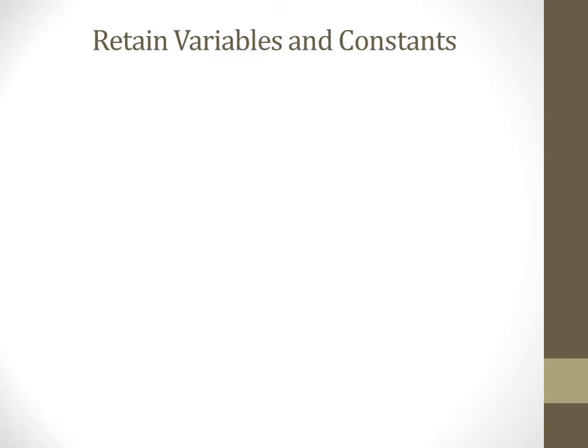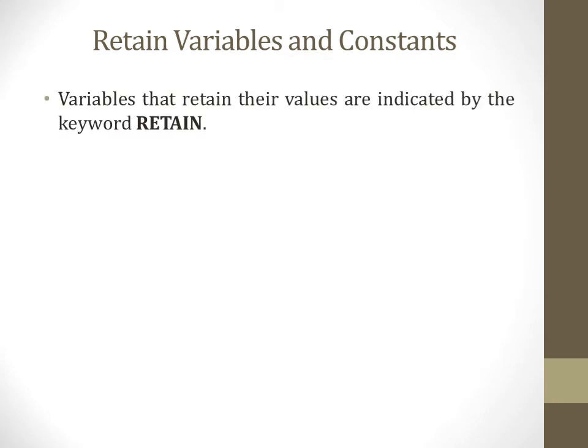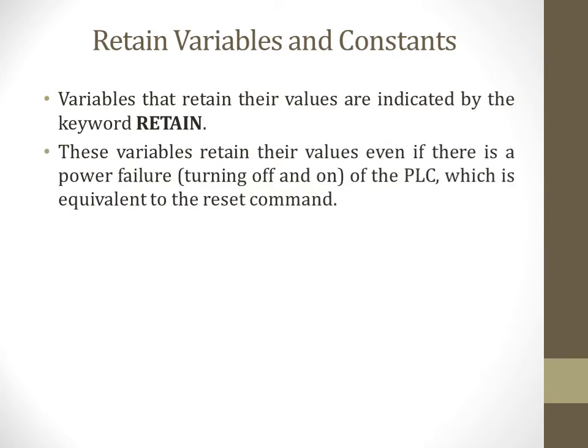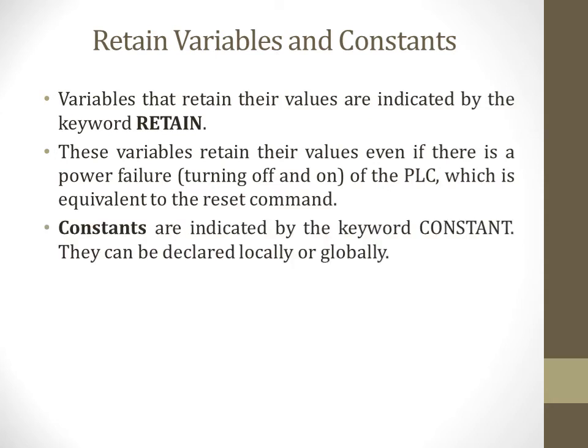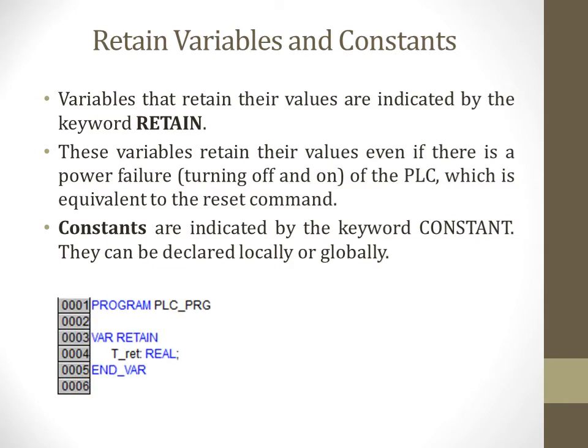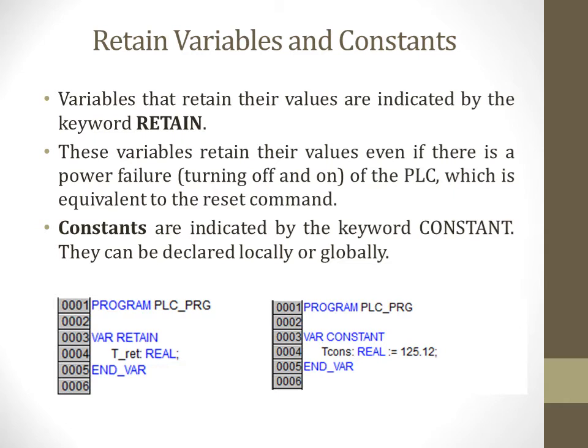Next we will speak about classification of variables. We have two types: retain variables and constants. Variables that retain their values are indicated by the keyword RETAIN. These variables retain their values even if there is a power failure — turning off and on of the PLC. Constant variables are indicated by the keyword CONSTANT and can be declared locally or globally.